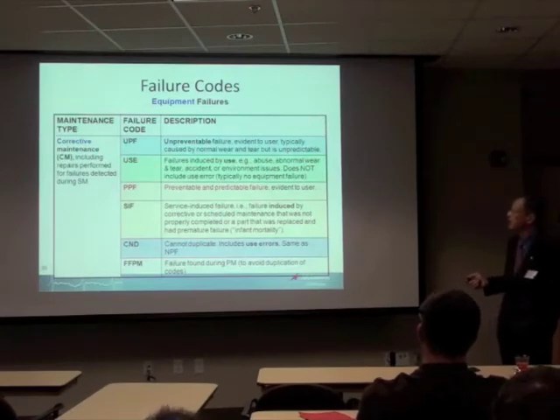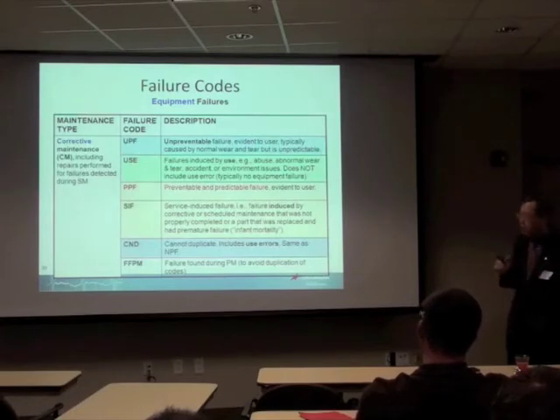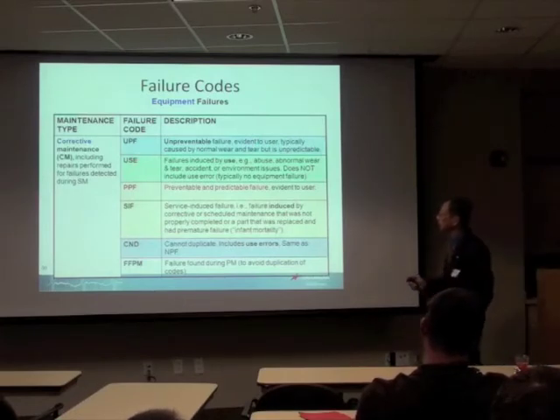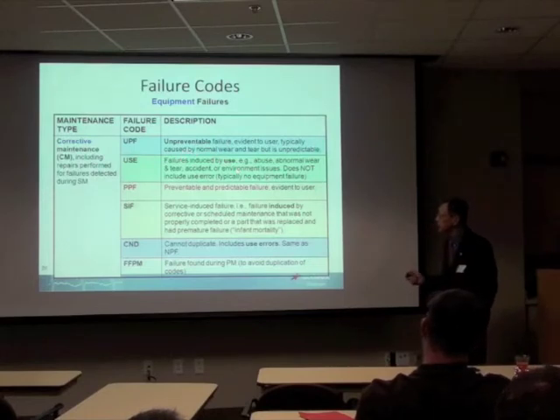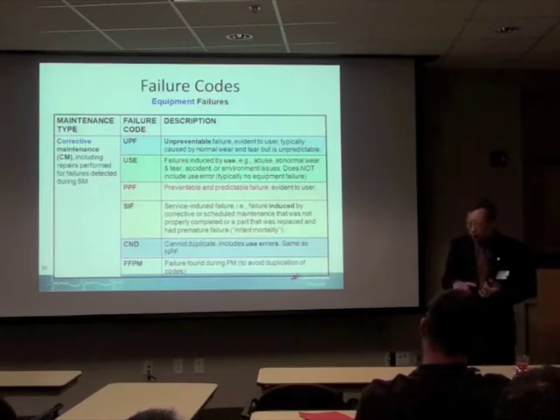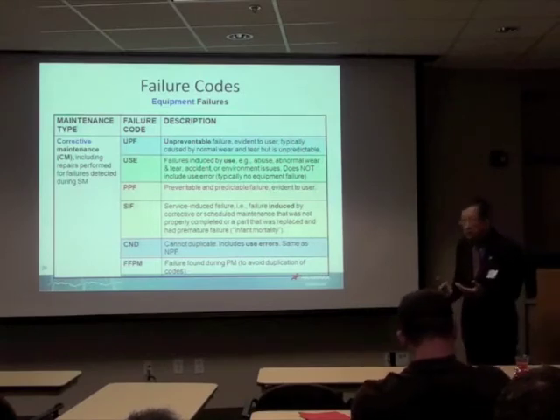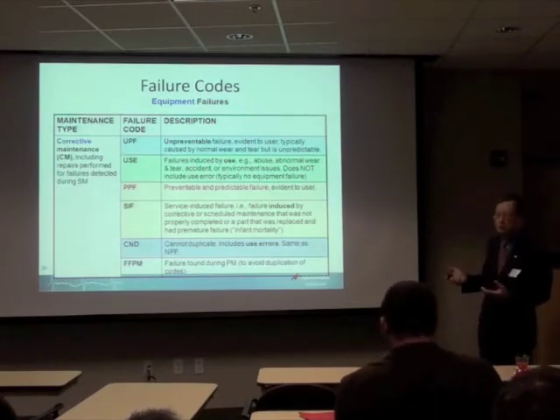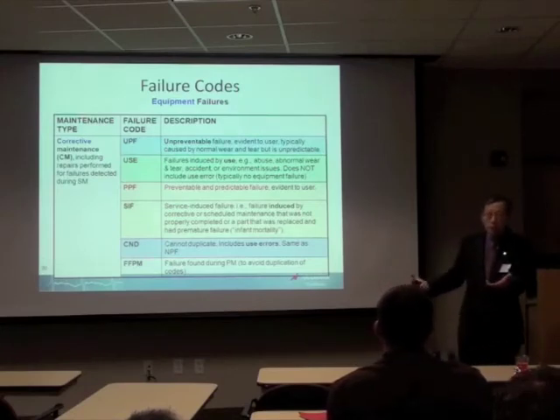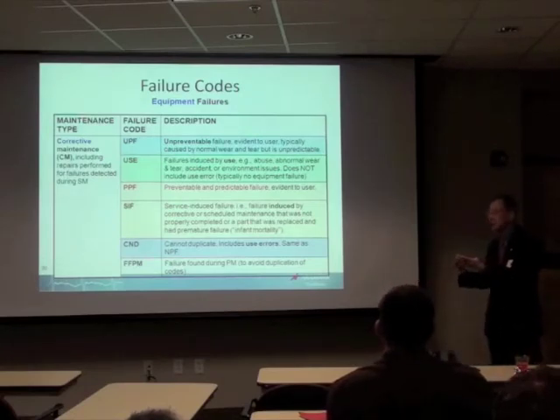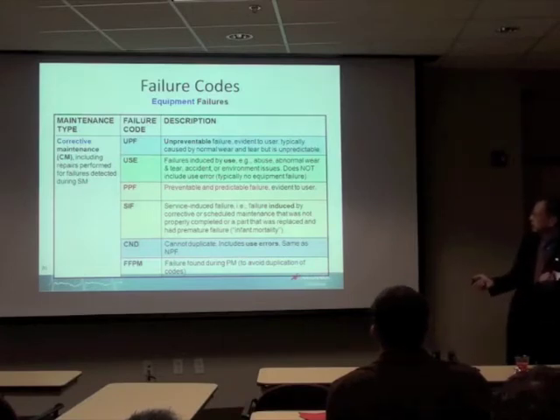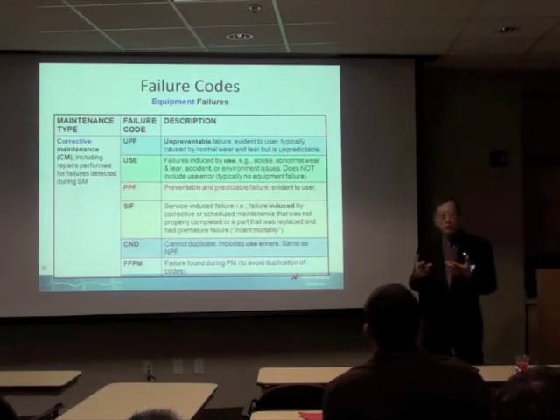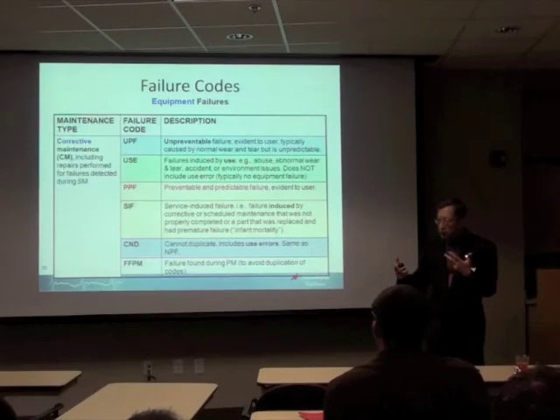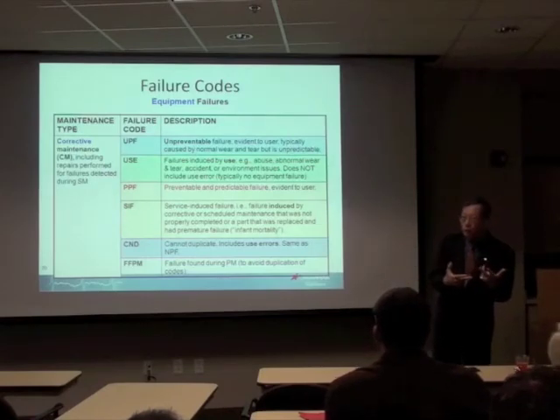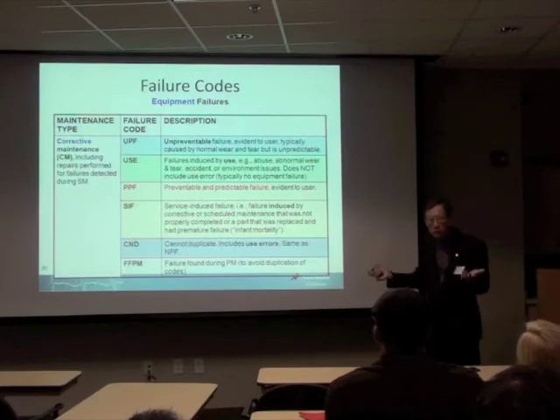Now, there are a number of failures associated with use. This is not user error, don't get confused here, okay? These are defects induced by use: abuse, somebody forced something there, abnormal wear and tear, heavy use, accident, somebody dropped the infusion pump on the floor, broke - yeah, of course it's broken, but it was not because the equipment itself failed. It does not include use error, because use error is typically a misconception of how the device should work, and then it was programmed in the wrong way, and you have a problem there, but the equipment did not fail by itself.